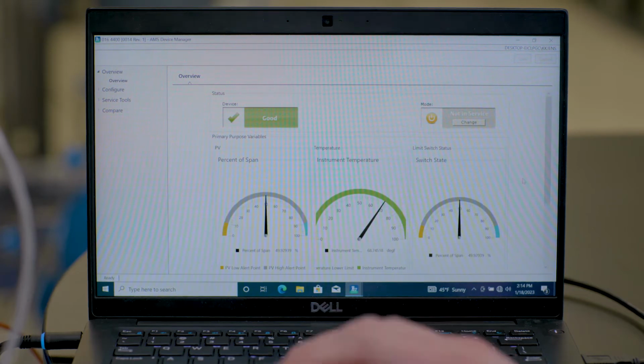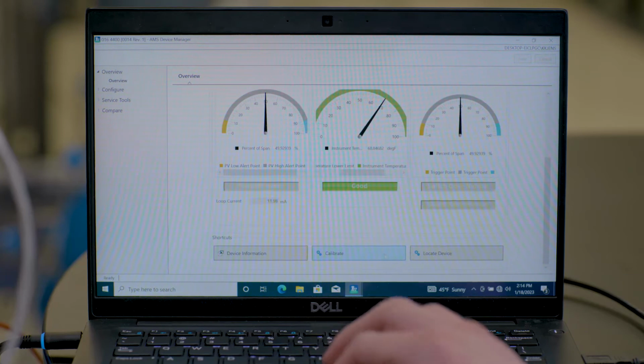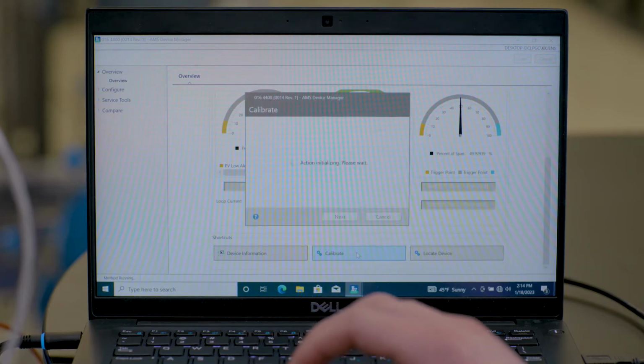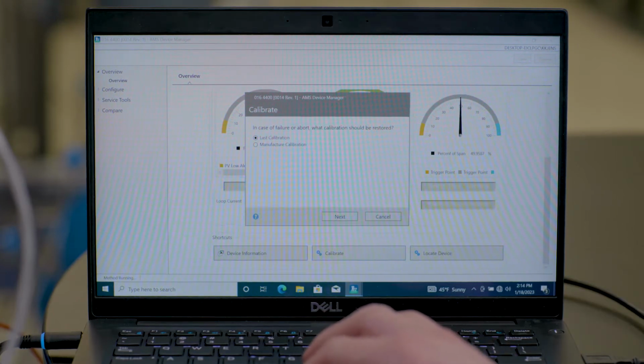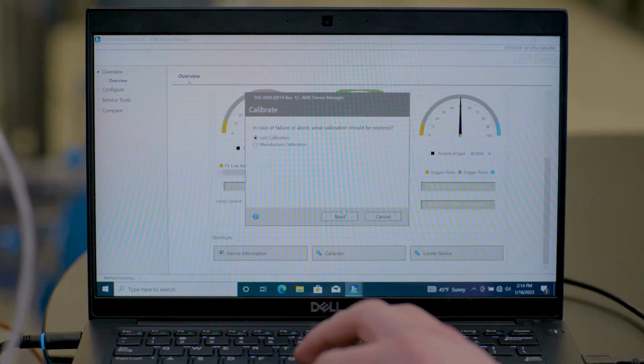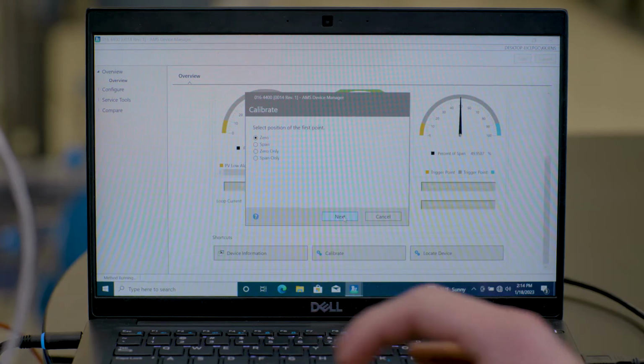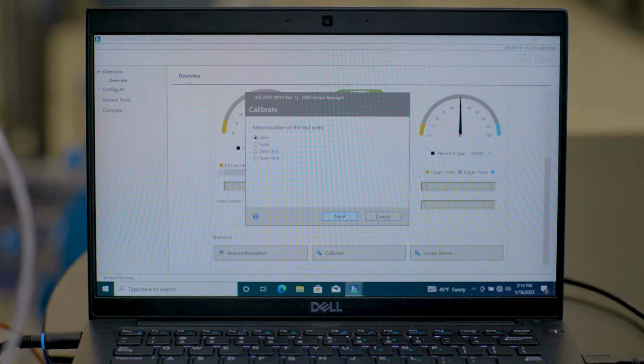The first thing you want to do is take the valve out of service, and then you can start the calibration process. You'll just hit calibrate, and a pop-up will come up that walks you step by step through calibration. As we go through this, we're going to set the zero first, but you can either set the zero or the span first.